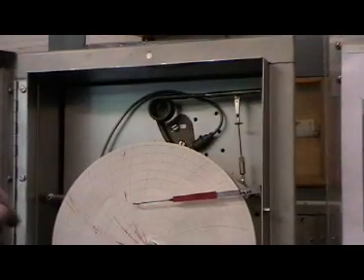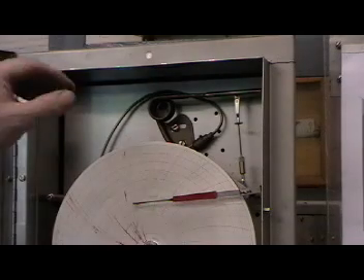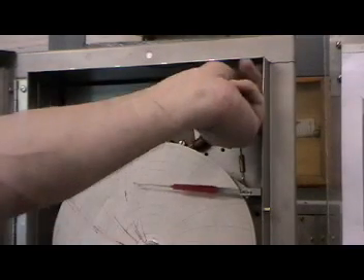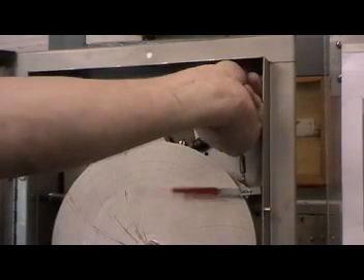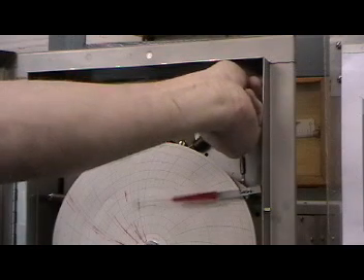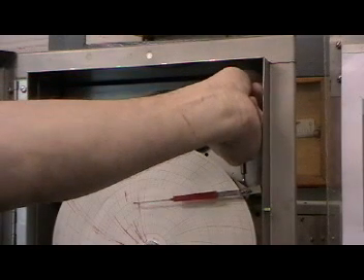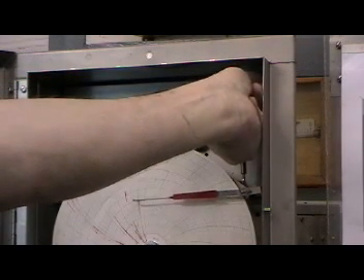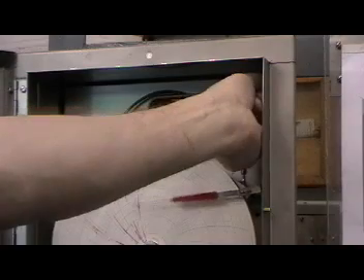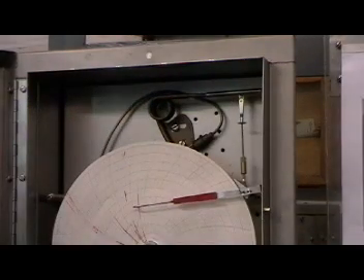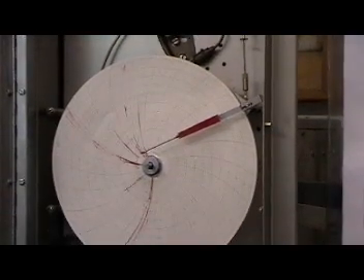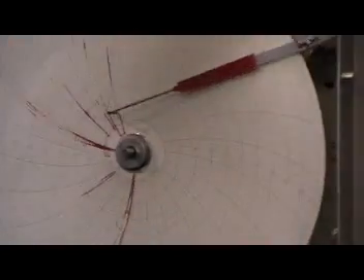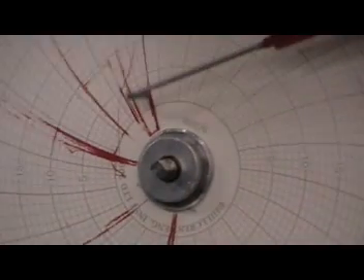But now we're going to need to, I'd already downspan the instrument, because that has an adverse effect. So, by increasing the span now, back to approximately where I know we should be. I know that because we've got some calibration paint on. We'll go back to zero again, re-zero the recorder.